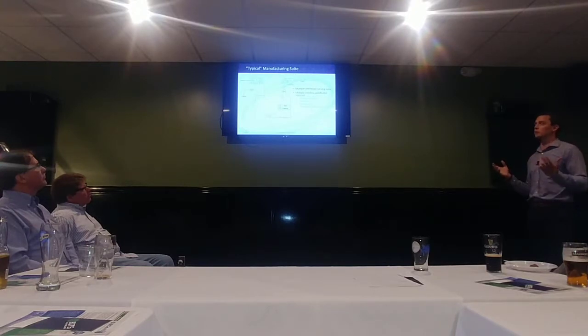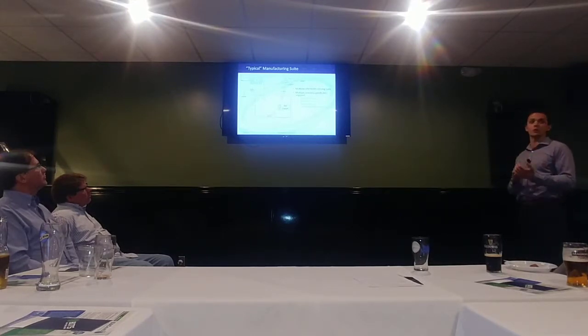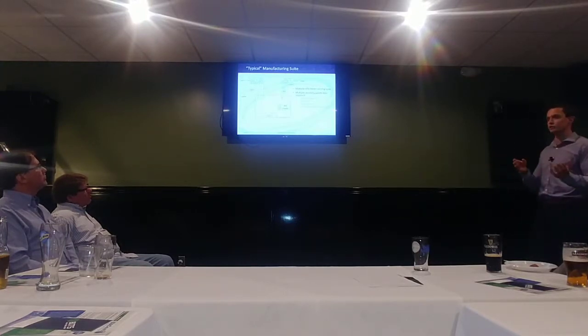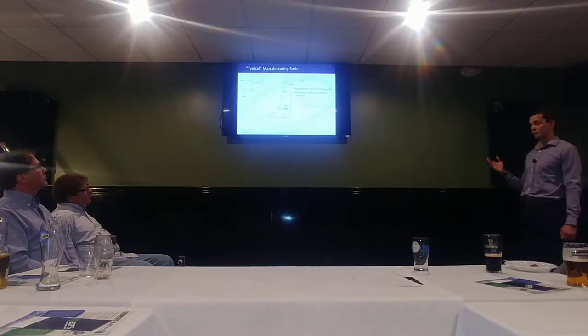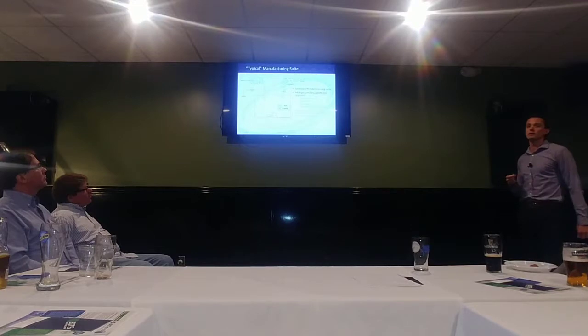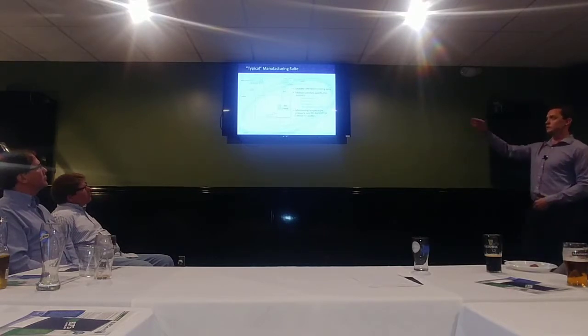There are also multiple ancillary points required. So you have room DP, you have your control parameters of return temp, return humidity. You may have a door switch to lock the control loop open if someone opens a door in an active pressure scenario. You may be monitoring equipment in the room. Next bullet point there. So maintaining your critical parameters is absolutely critical to the product quality. So the product's dependent in these rooms on temperature, pressure, humidity, amount of air changes.